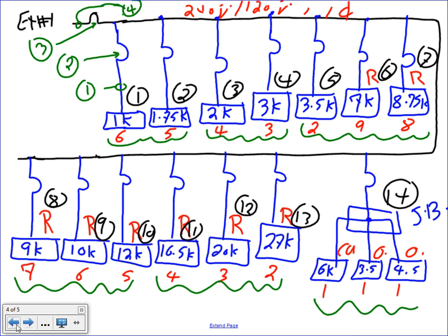Oh, okay, because it looked like you have an overcurrent protection device and then 6 ranges at 1K. So this number is the calculation number. This is the branch circuit. This is the overcurrent device. And I'm going to do them all for the branch circuit, then go do it for the feeder. The ones in black, that's just our reference for the calculation. So we don't care.